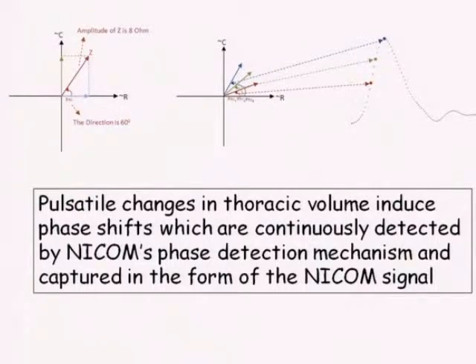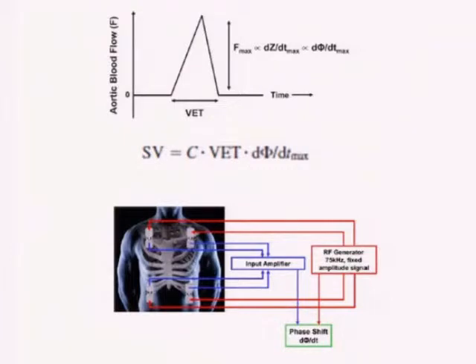So pulsatile changes in thoracic volume, which is stroke volume, induce a phase shift, which are continuously being detected by NICOM's phase detector mechanism and captured in the form of a NICOM signal. So instead of looking at the change in amplitude of the signal, it looks at the change of phase, which is the angle, and that's related dynamically to the stroke volume in the thoracic aorta. So this is schematically what it looks like. You have 2 electrodes on each side, an emitting and a receiving electrode. This is the formula for stroke volume, which is a constant times the ventricular ejection time, which it gets from the EKG signal, and that is the phase change. So it's the phase change over time.